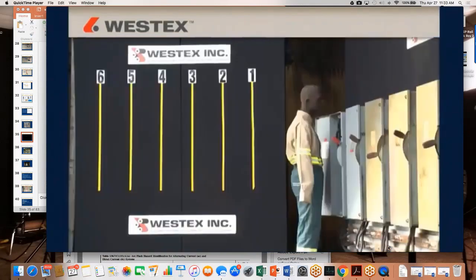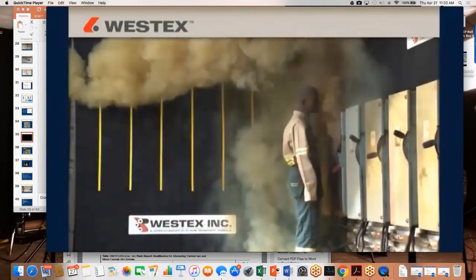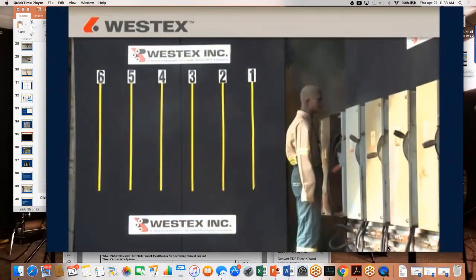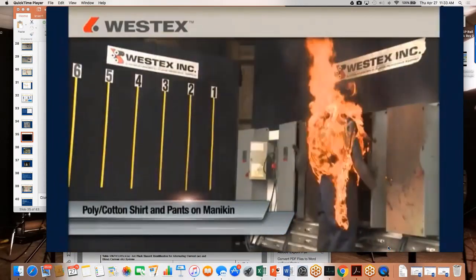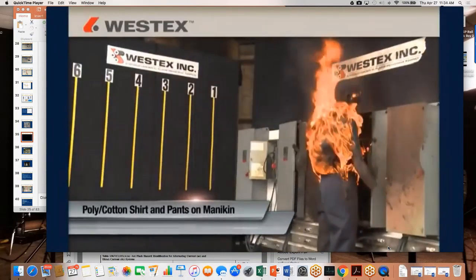The learnings illustrated by the events in this video clearly demonstrate that industrial arc flashes are extremely hazardous events, despite lower voltage versus utilities, and that there is no situation, regardless of hazard analysis data, where you can be assured that non-flame resistant clothing will not ignite, regardless of whether the fabrics are blends or 100% cotton.